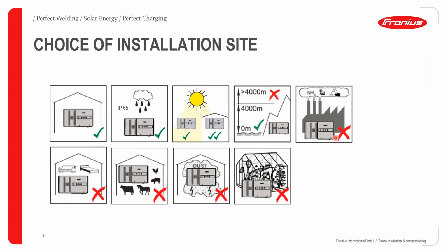Again, please don't install the inverter in a highly toxic environment, such as a factory where maybe there's a lot of ammonia in the air. The reason for this is the Fronius inverter has an active cooling system where it actively draws in air from the environment and passes it over the power electronics. So if you're passing ammonia into the inverter, it could lead to degradation of your power electronics.